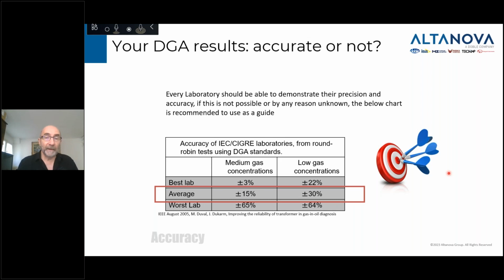Just to show you the impact of having a good lab versus not such a good lab. Quite a few years ago, IEC Cigre did a round-robin test. What they did is they asked labs around the world, around 130 labs, if they would like to be in that study, and almost all of them said yes. So they sent those labs what we call a gas in oil standard. It's a specific oil in which a specific quantity of gas has been dissolved very, very carefully, to a very tight spec. They sent those samples with no information on them, just an oil sample as it is, to those labs.